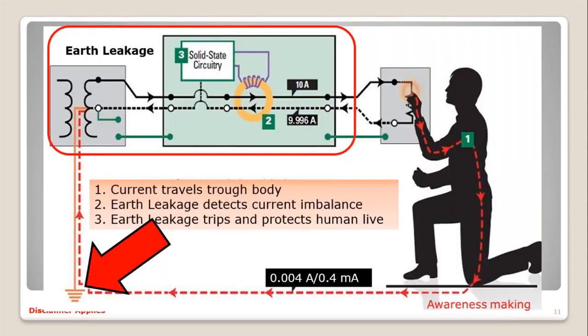So the earth leakage, as the name implies, detects imbalanced currents. That's how it protects you or protects the equipment. When there's an imbalance in current through the earth leakage, it will give a tripping function. That is the part where, even if you're showering and you have a tickling feeling through your body, this is what's happening. So if the earth leakage is earthed correctly, it will pick up that leakage current and trip before it gets too high and you get hurt in the process.